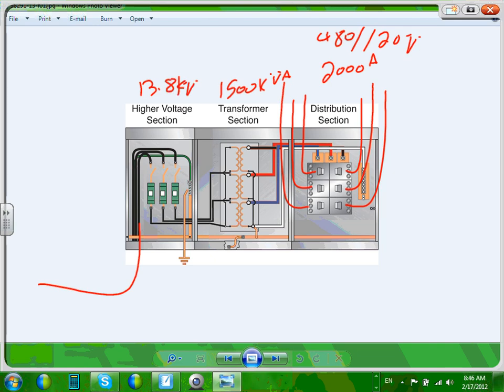So you have a high voltage section, disconnects and fuses, and that's going to a transformer that transforms it from a high voltage 13,800 volt into a 208/120, or 480/277. This probably happens in bigger buildings where the utility brings you a feeder at high voltage, and the utility will have control over the high voltage section, and you have control over the low voltage section. Sometimes the transformer and the high voltage section are part of the utility. Not commonly used, as I said, except in major projects.